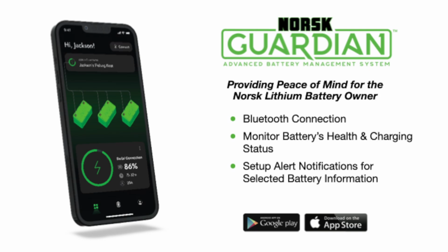You're going to be able to monitor the health of that battery. When one of our batteries starts up and you connect to the app, it actually runs it through a set of diagnostic checks to make sure everything is functioning the way it's supposed to. Compare that with a lead acid battery, where you just kind of hope it's going to work. It either does or it doesn't, and if it doesn't, it's time to replace it. These lithium batteries with the connectivity, you can diagnose just about any issue, right down to loose connections, blown fuses, bad battery charger, with that type of monitoring.